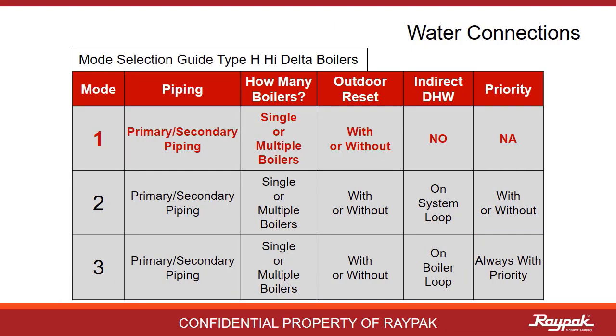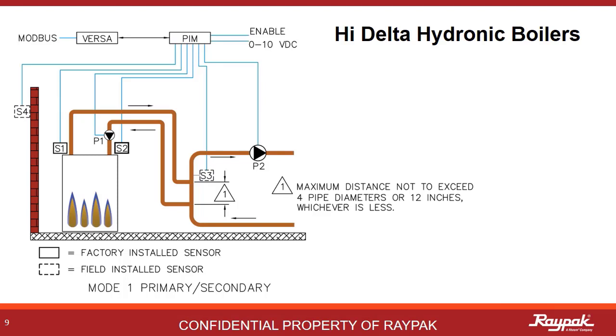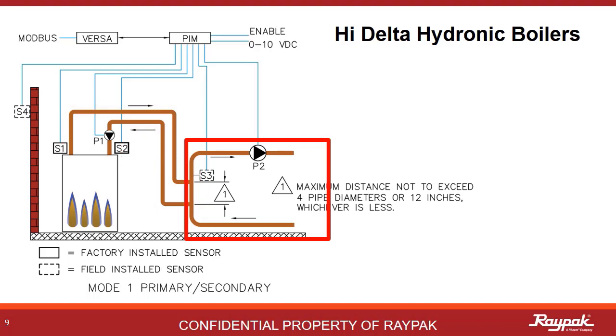First, we will present Mode 1 with primary-secondary plumbing — by far the most common configuration on a hydronic boiler. Here is a drawing for a Mode 1 primary-secondary system with a single boiler. It is primary-secondary because there are two loops: the boiler loop and the system loop. That is how you should refer to them — the boiler loop and the system loop, not the primary loop and the secondary loop. The place where the two loops overlap is called the decoupler. The decoupler is the magic of a primary-secondary system. When built properly, this will allow the bigger system pump to run when the boiler is not running without forcing water through the boiler.